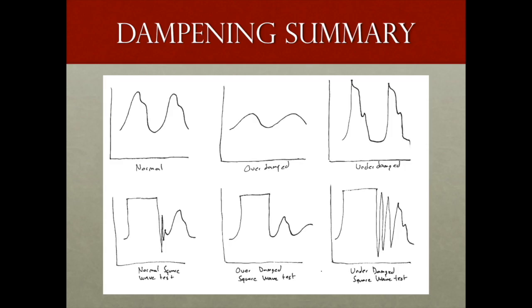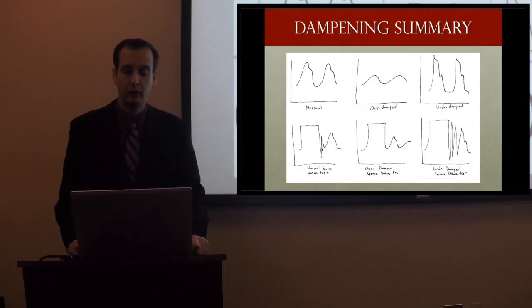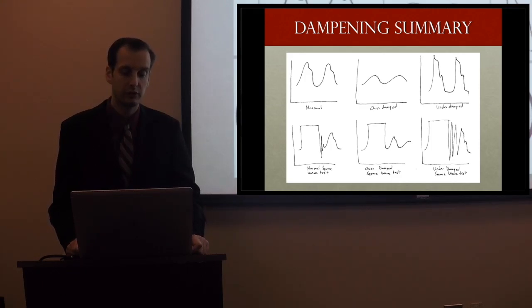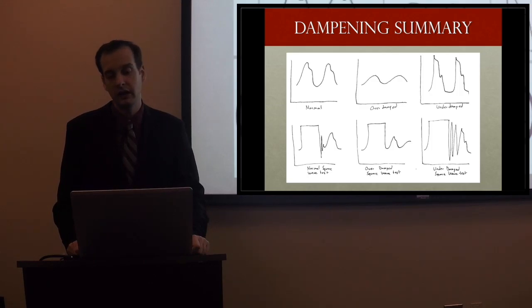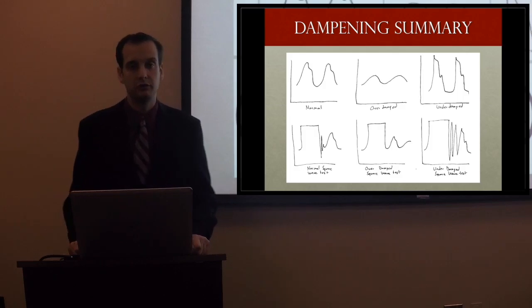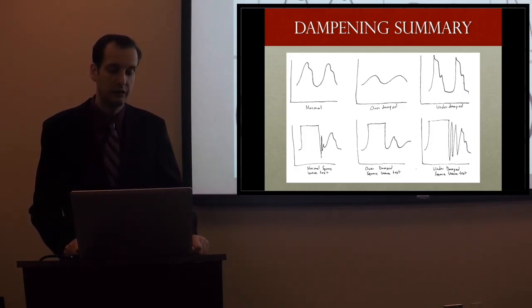Putting all of them next to each other, we can see a normal arterial tracing followed by a normal square wave test, then an over-dampened arterial tracing followed by an over-dampened square wave test, and an under-dampened arterial tracing followed by an under-dampened square wave test. You can see how over-dampening narrows your pulse pressure, causing you to believe you have a lower systolic and higher diastolic pressure, while underdampening does the opposite—it widens your pulse pressure and leads you to believe your systolic is higher and diastolic is lower.